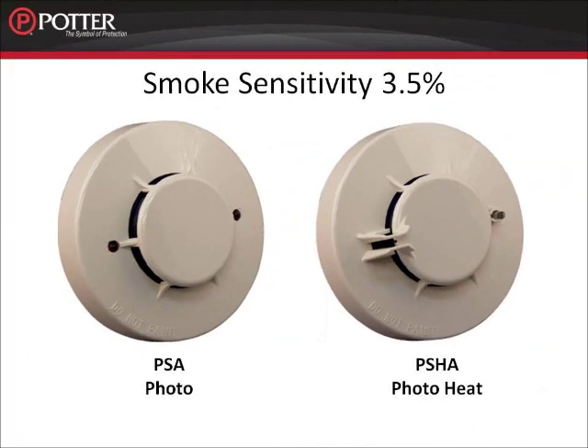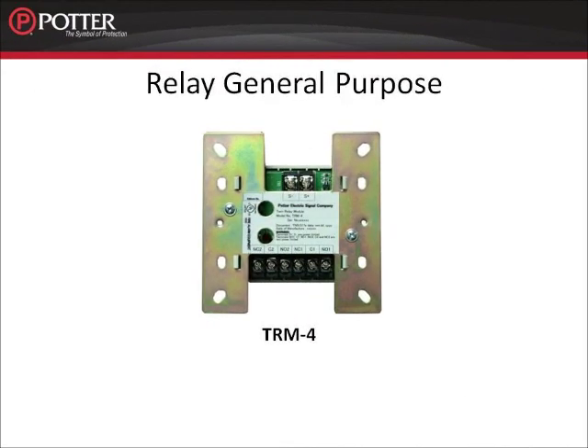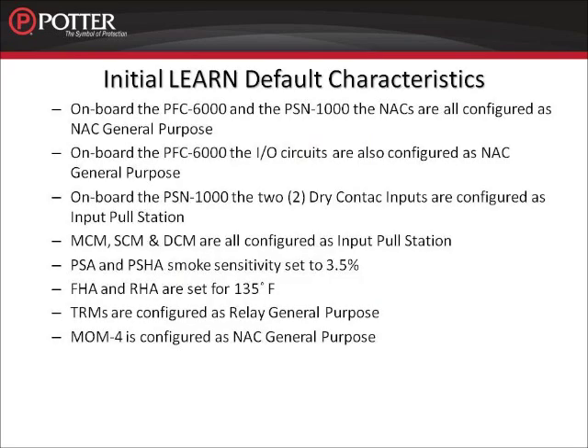The PSA is configured as a photo, and the PSHA is configured as a photo heat. The initial smoke sensitivity for these smoke detectors is 3.5%. The FHA is configured as heat fixed and the RHA is configured as heat combo. The initial alarm threshold for these heat detectors is 135 degrees Fahrenheit. The TRM module is initially configured as a relay general purpose, and the MOM4 is initially configured as a NAC general purpose device.